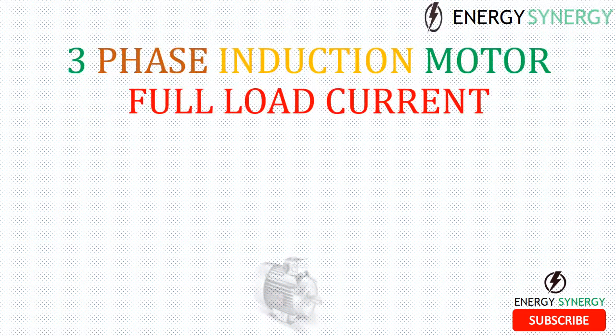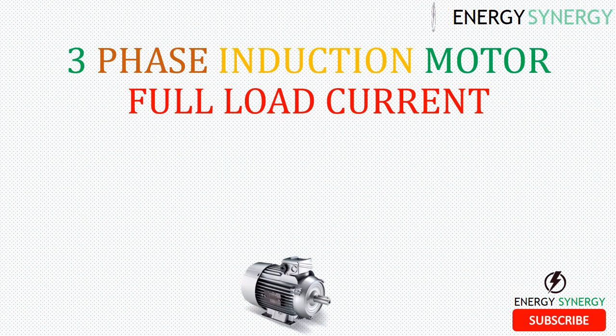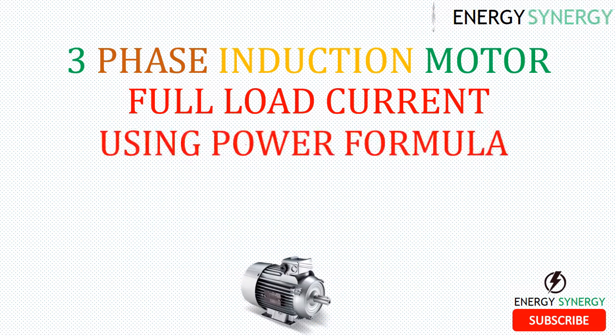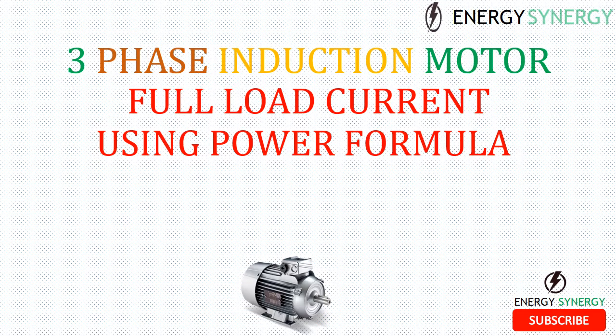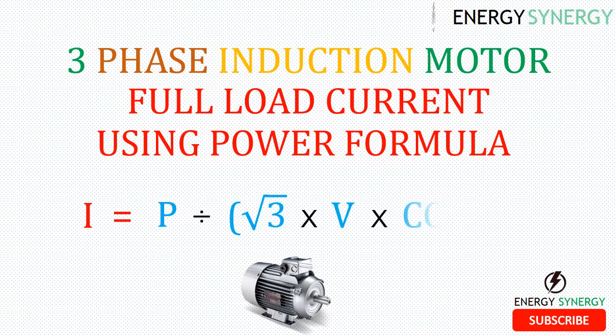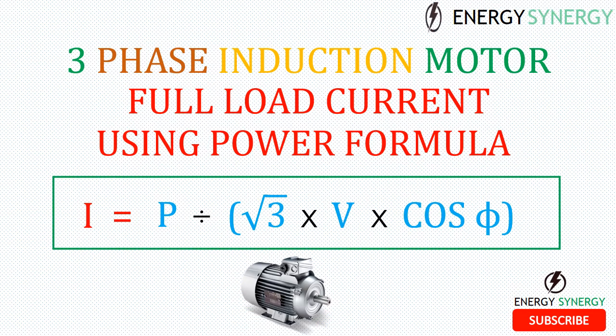It is very much required to calculate the full load current of induction motors. The formula for calculating full load current of a three-phase induction motor is: Full Load Current = Power / (√3 × V × cos φ), where power is in kilowatts and current is in amperes.